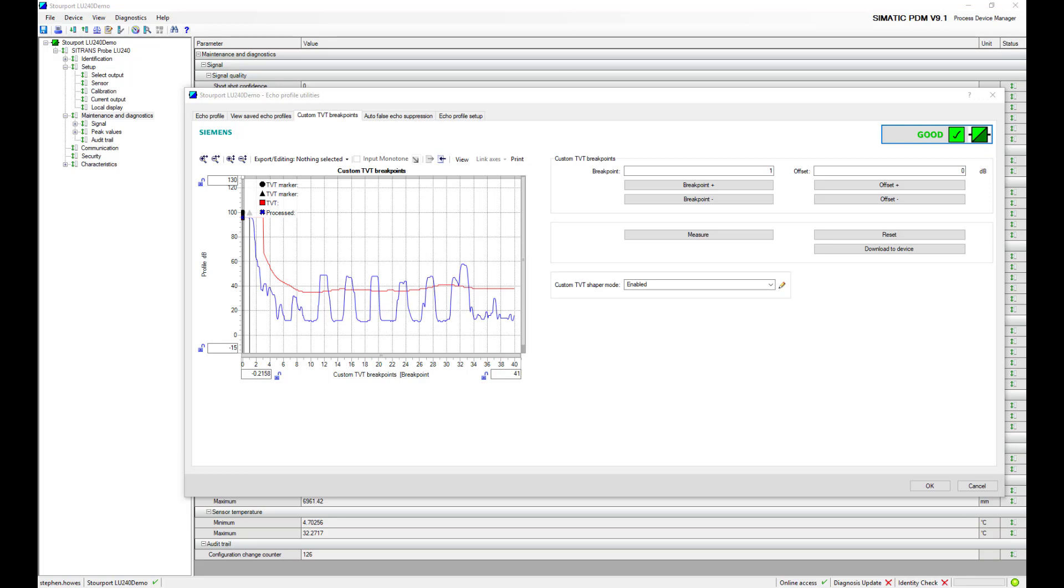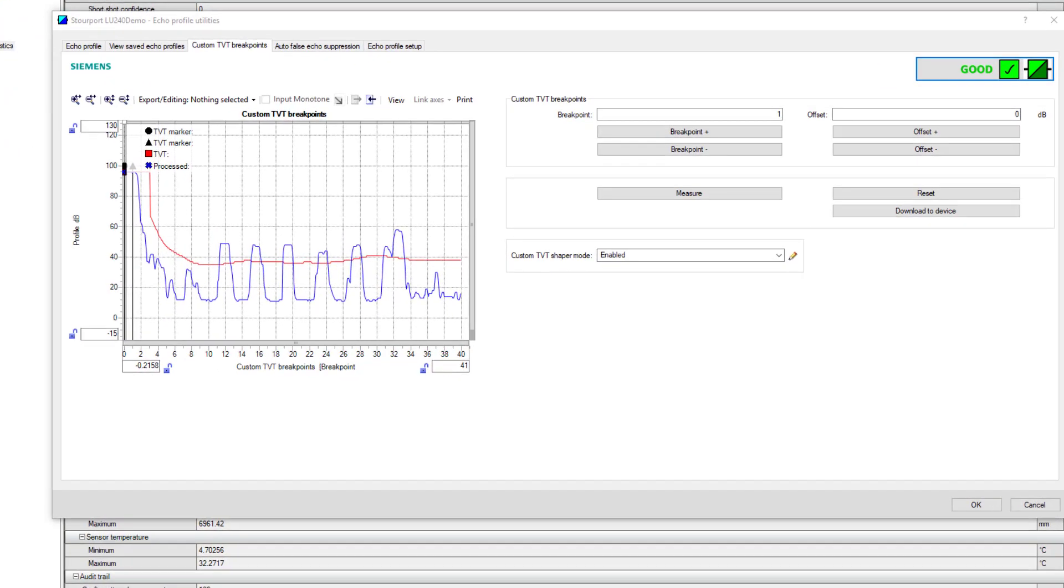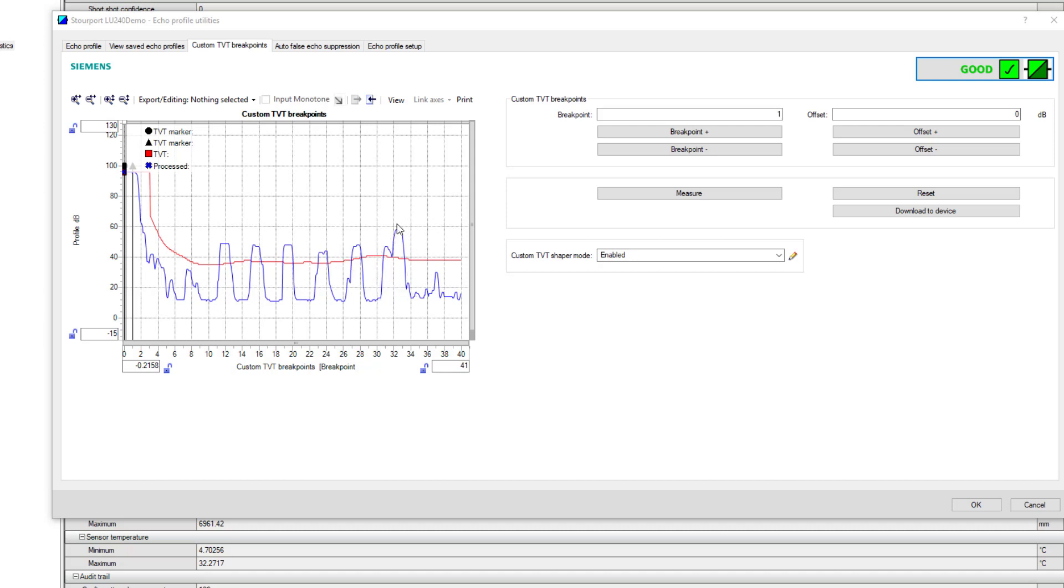Here we have a standard feature for Siemens level devices, manual TVT shaping. It's extremely rare that you have to do this but I'm showing you this as part of a training exercise. Remember what we said, the echoes are scored above the red line and they're done on height, area, and whether they're first, second, third or last. What we have to do is increase the score of the true echo which is this last one and decrease the score of these.